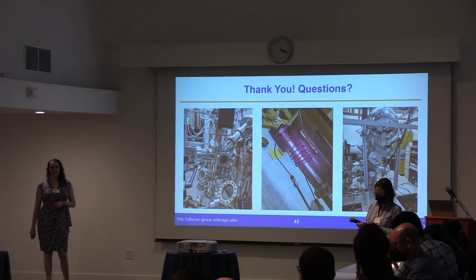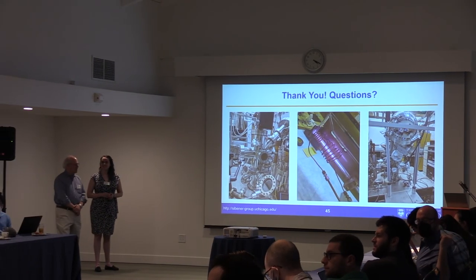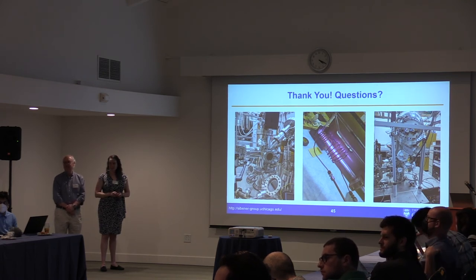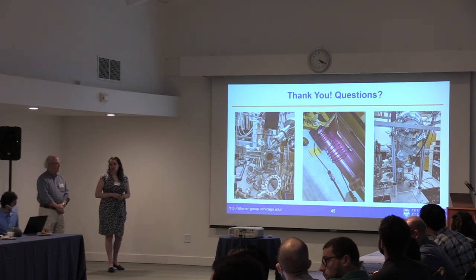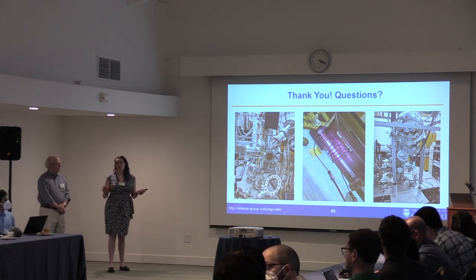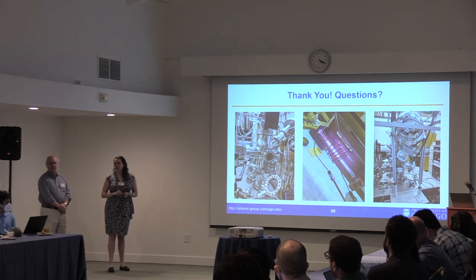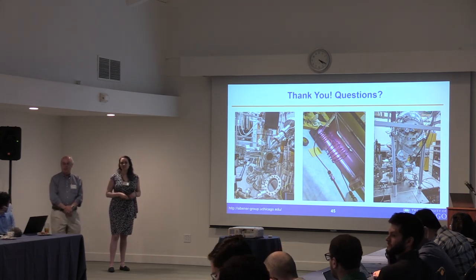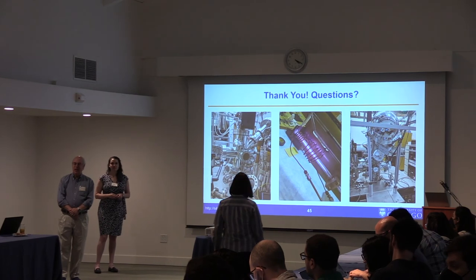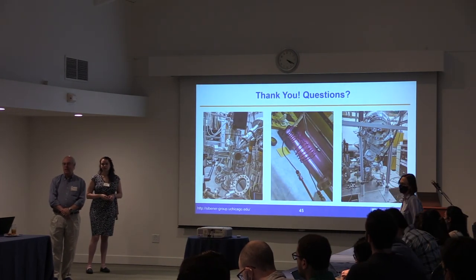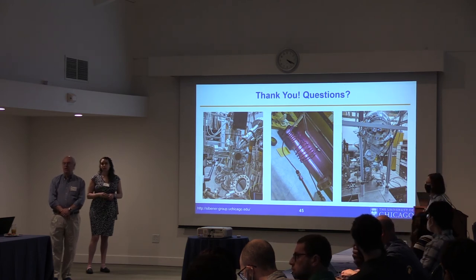We have time for a couple of questions. How low does XHV go? It can be difficult to figure out just from pressure gauges, but generally the XHV regime is around 10⁻¹² to 10⁻¹³ torr, meant to mimic interstellar or NASA outer-space chemistry. An additional comment: what you're frequently concerned about is the partial pressure makeup. In some labs you care a lot about having no helium, so your detector is designed to a partial pressure of about 10⁻¹⁴ — the absolute pressure may be higher, but the helium partial pressure is much lower.